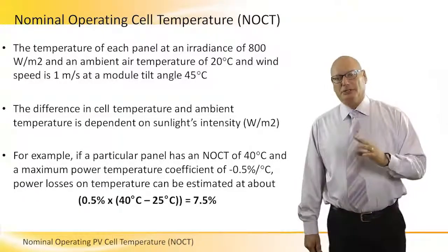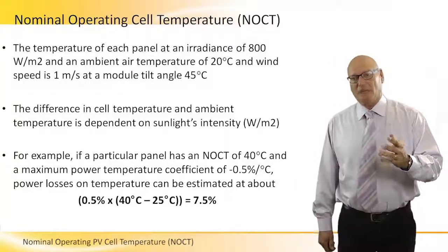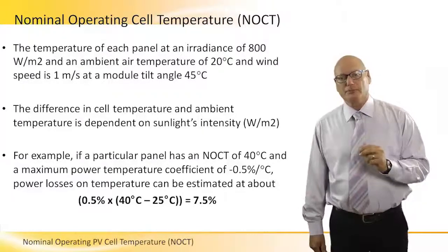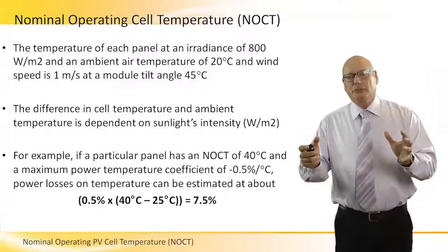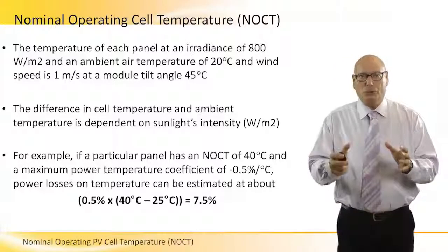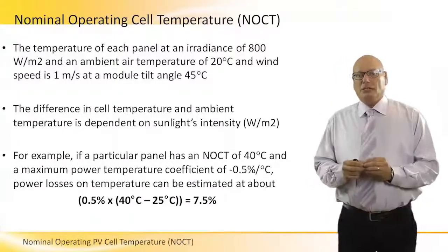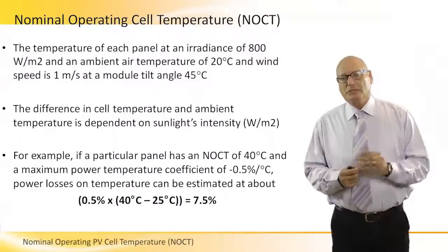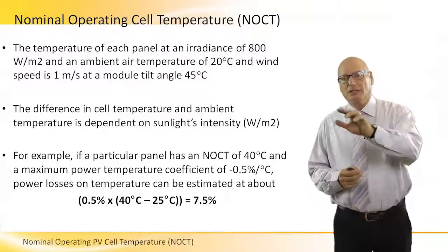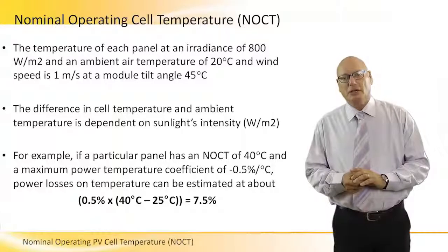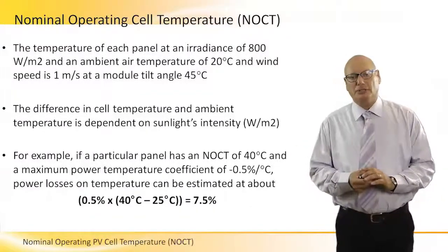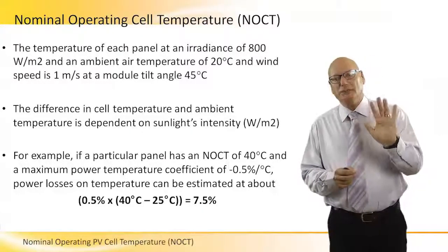A very important parameter when we look at the cell and the panel is what's called NOCT — Nominal Operating Cell Temperature. The standard for verifying whether a cell is good or bad involves testing under standard conditions: 800 watts per square meter irradiance, ambient air temperature of 20°C, wind speed of 1 meter per second, and a module tilt angle of 45 degrees to the sun.